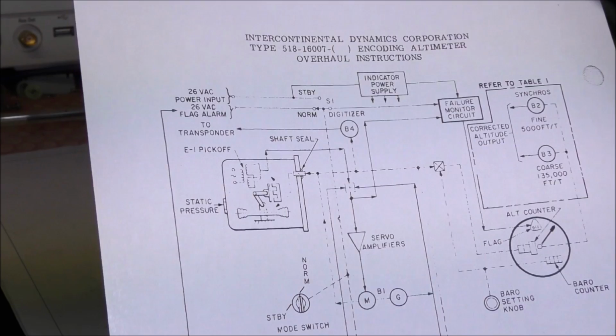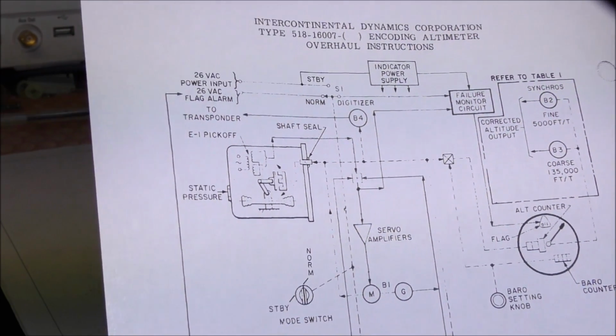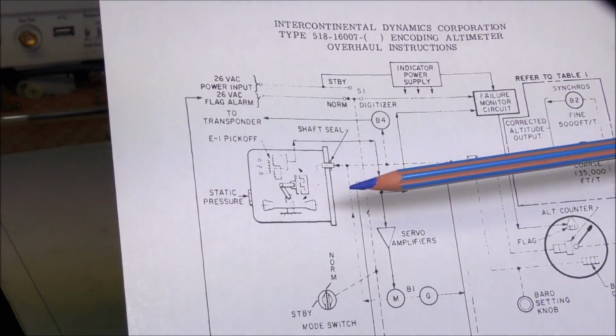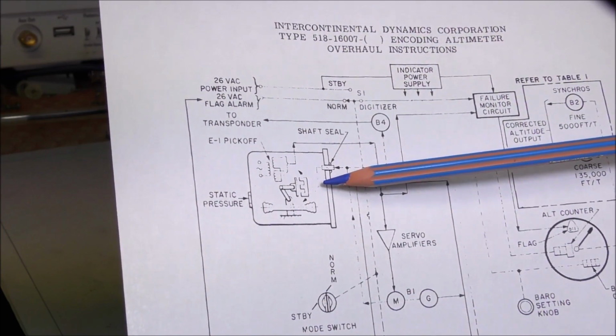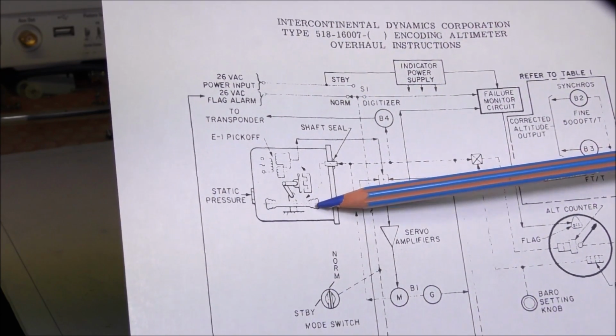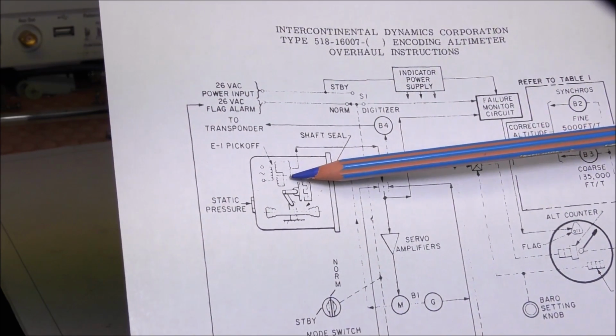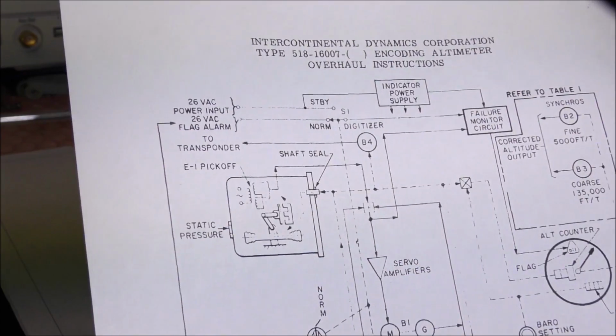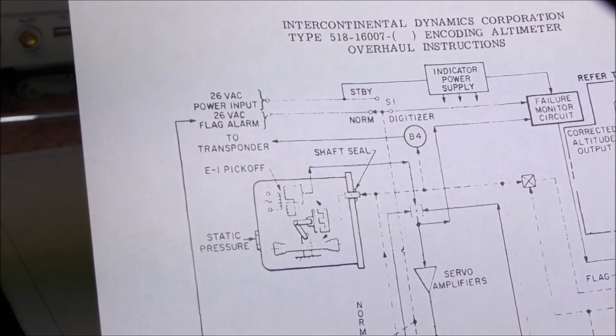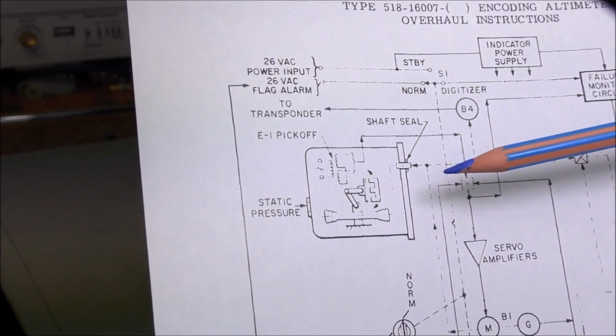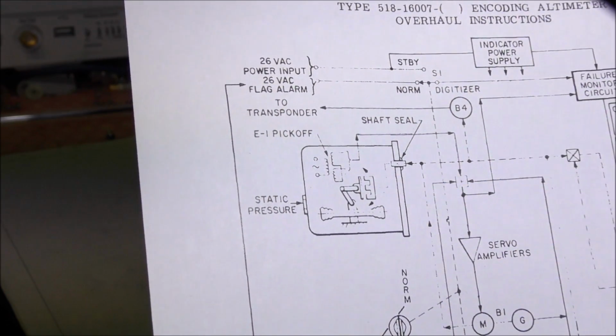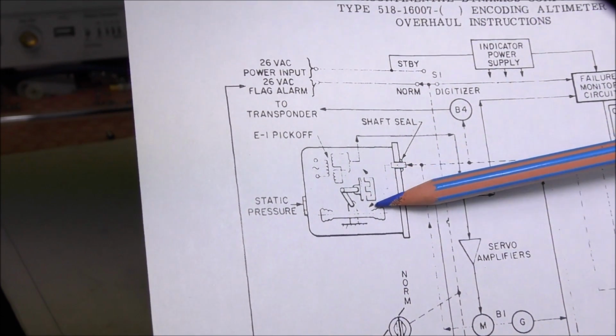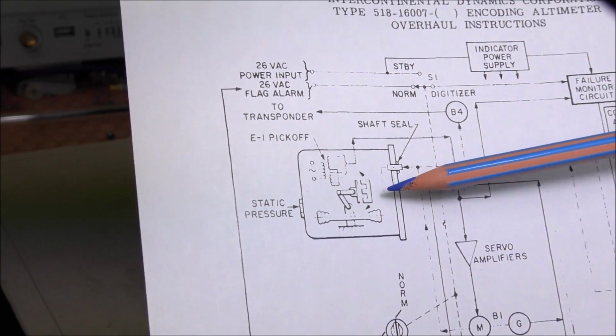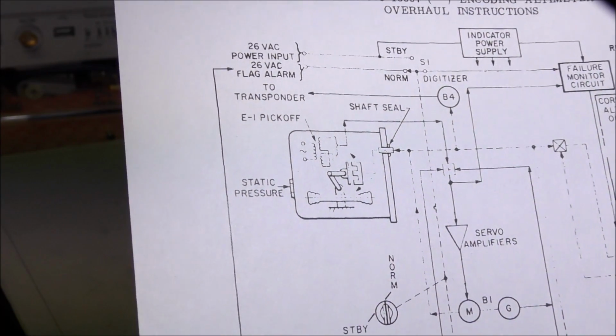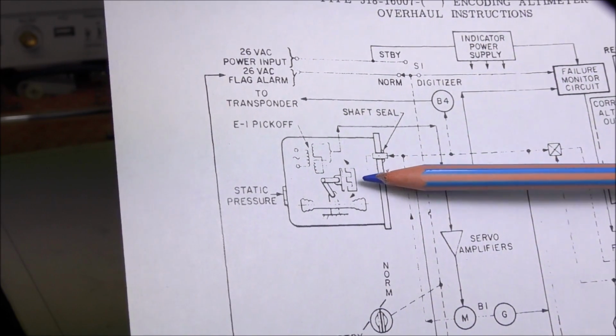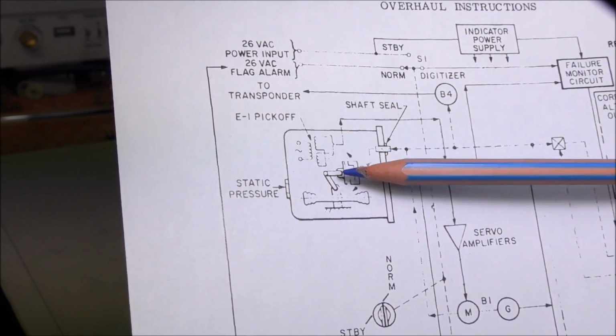It is not complicated. It is the servo control loop as usual. So this is the transducer here. So the transducer is composed of an aneroid capsule here, and there is a pick-off sensor, which is a kind of LVDT sensor. This is something which is common on all these kinds of transducers. One side of the pick-off sensor is linked to the capsule, and the other one, this E stuff here, is linked to a mechanical shaft. The sensor permits to measure the position of the E bar relative to the I bar.